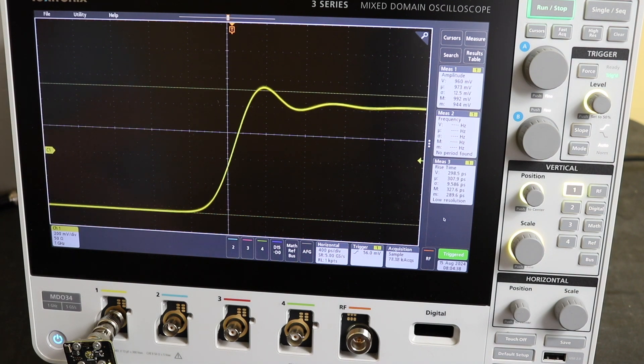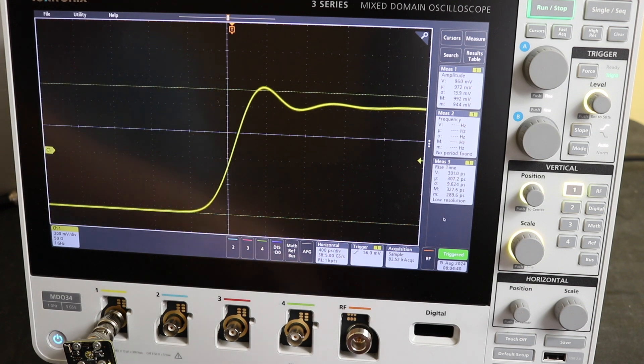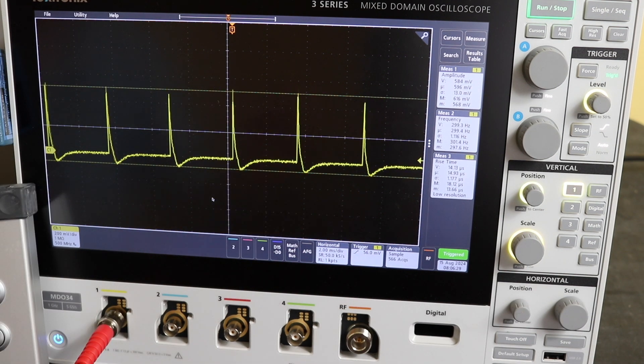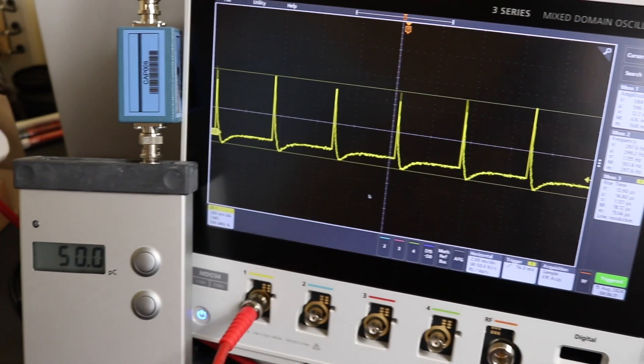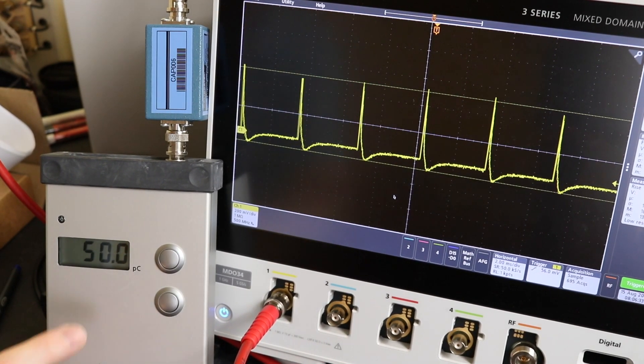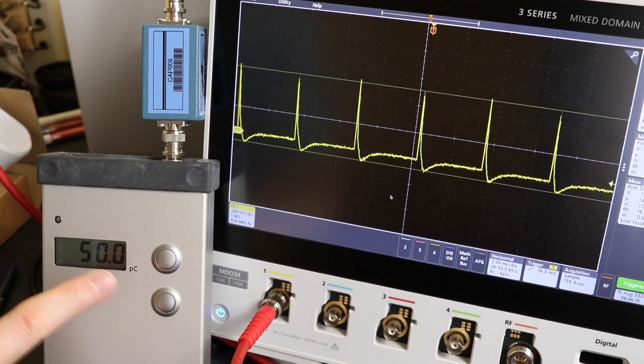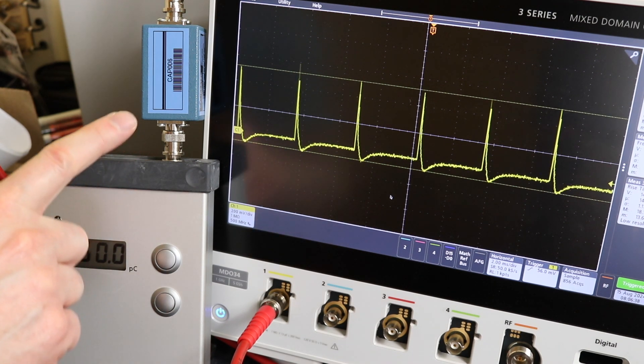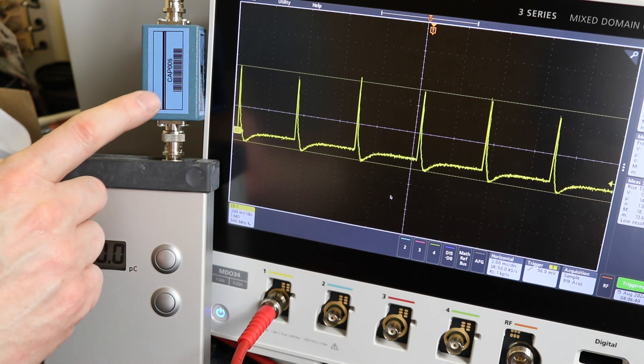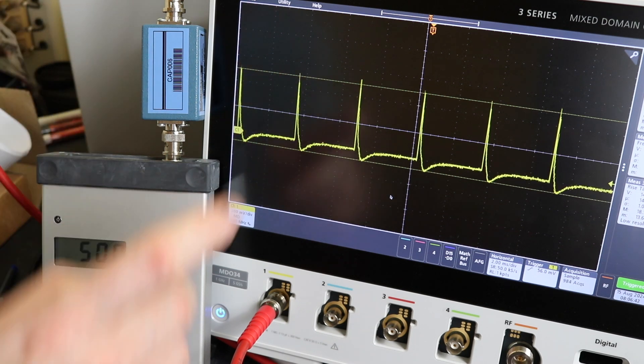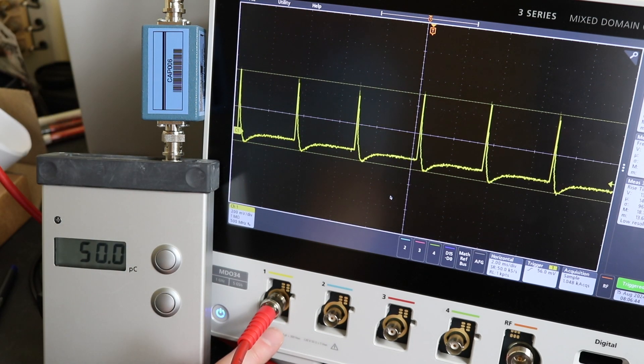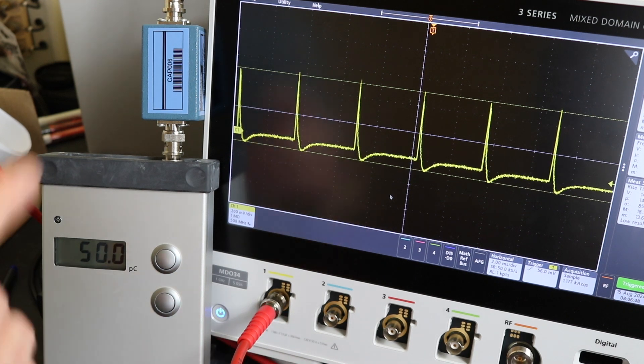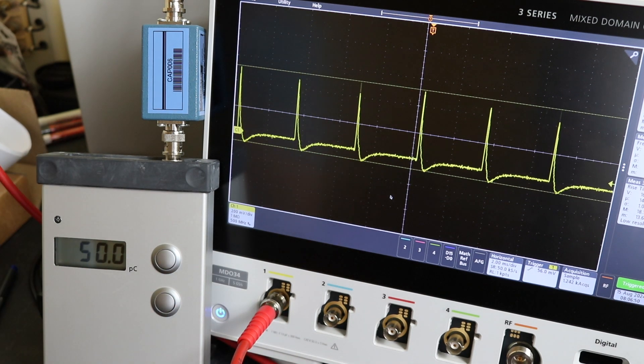Here's our pulses being generated from the Omicron partial discharge calibrator. There it is sat over on the edge here. I'm generating 50 picocoulombs. The test circuit for this: I'm putting this into a one nanofarad capacitor that is then connected over onto the input channel of the oscilloscope and that forms the circuit there.